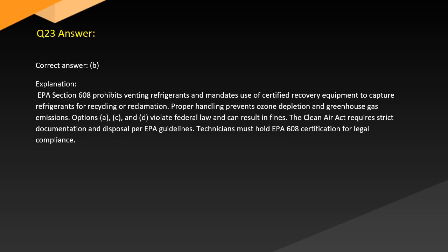Answer. Correct answer: B. Explanation. EPA Section 608 prohibits venting refrigerants and mandates use of certified recovery equipment to capture refrigerants for recycling or reclamation. Proper handling prevents ozone depletion and greenhouse gas emissions. Options A, C, and D violate federal law and can result in fines. The Clean Air Act requires strict documentation and disposal per EPA guidelines. Technicians must hold EPA 608 certification for legal compliance.